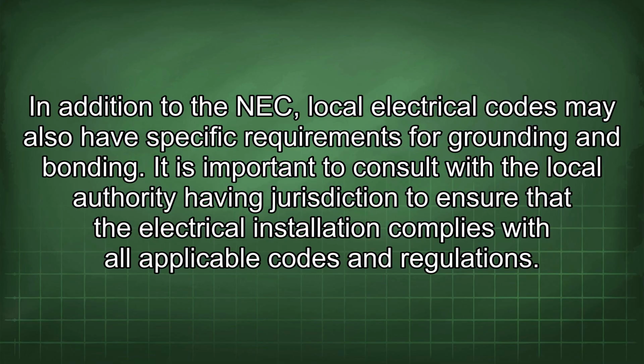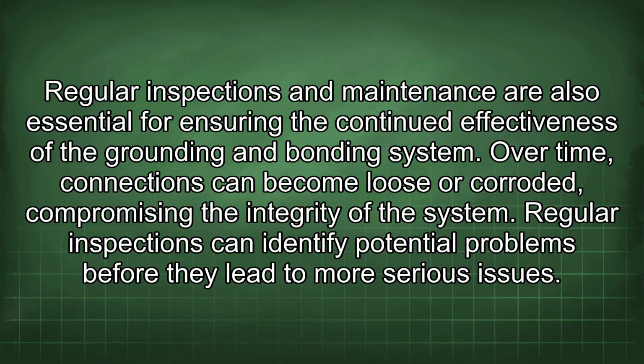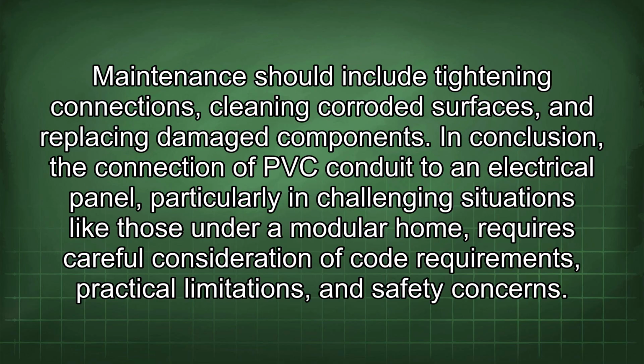Regular inspections and maintenance are also essential for ensuring the continued effectiveness of the grounding and bonding system. Over time, connections can become loose or corroded, compromising the integrity of the system. Regular inspections can identify potential problems before they lead to more serious issues. Maintenance should include tightening connections, cleaning corroded surfaces, and replacing damaged components.